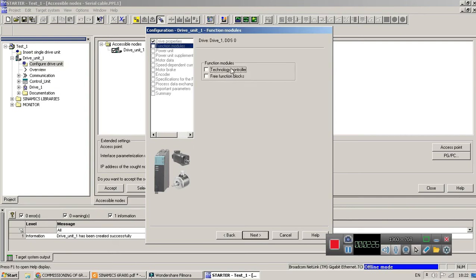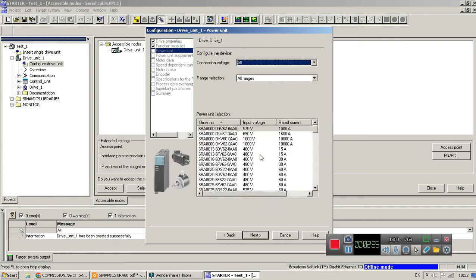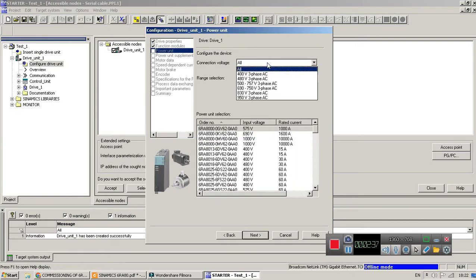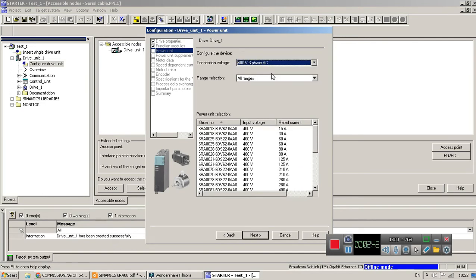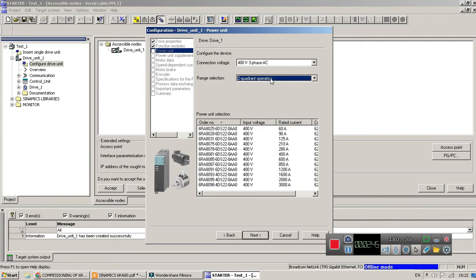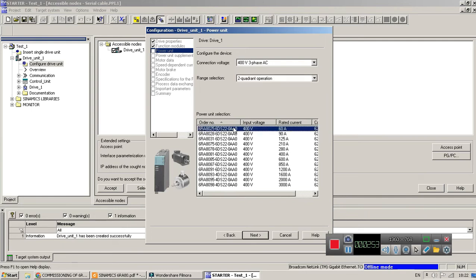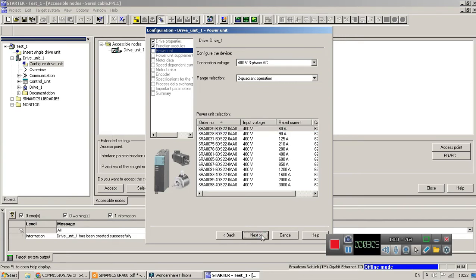Next, select which function module you are using - technology controller, free function blocks, anything what you want. If you want DDS, so next. Here you have to select your model. 400, I have 400 volt AC drive and 2 quadrant drive. Here you can see all the models listed below. Select - my model is 6RA80256DS22 and that model is displayed on your unit front sticker. And then select this.